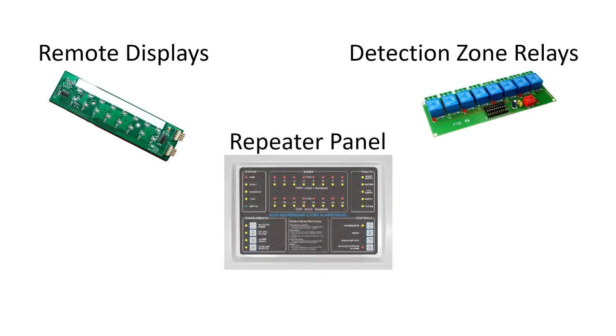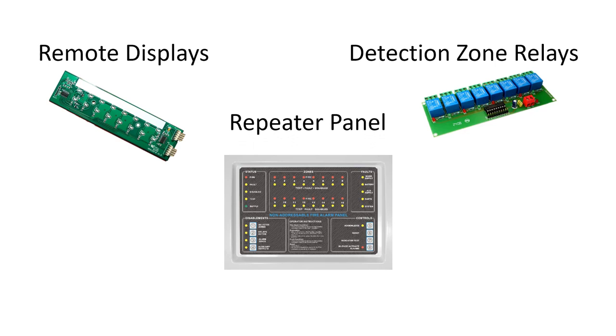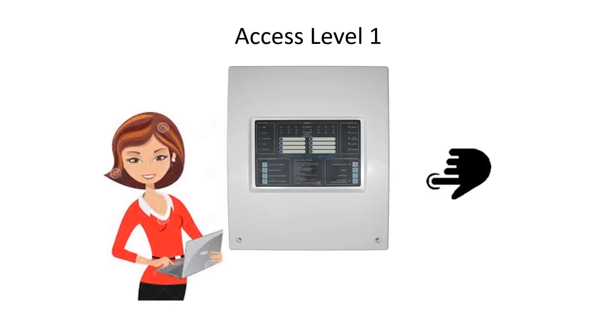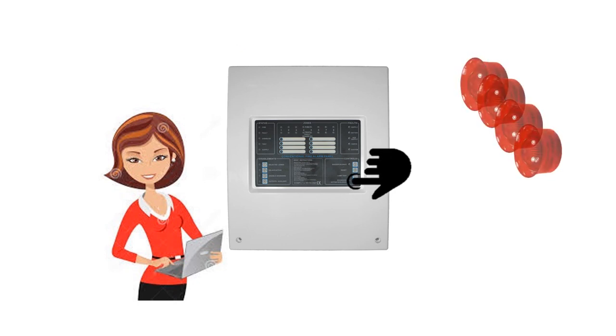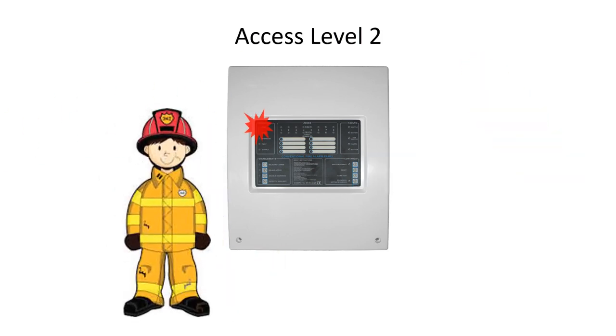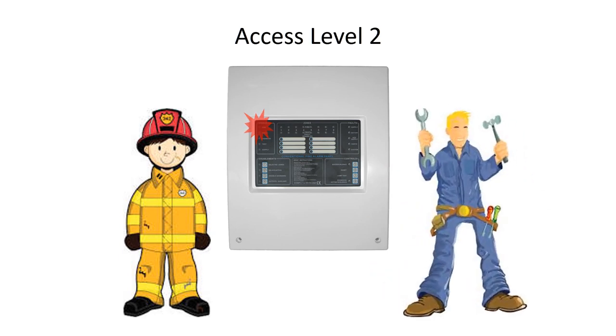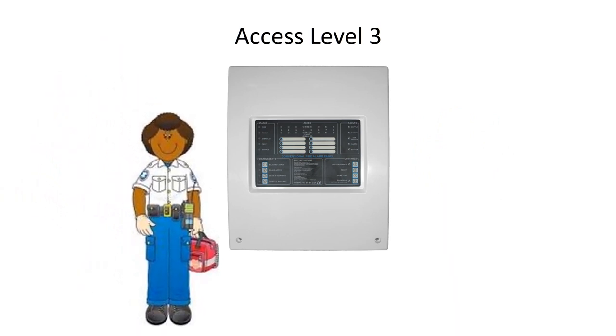A repeater panel extends the panel's controls and indicators to another location. Full control is available at the repeater panel, but no detectors or audio-visual alarm devices are connected to the repeater panel. The panel has 3 access levels that provide the required functions for the appropriate user. This may be an employee who needs to activate the audio-visual alarms to evacuate the building, or the fire brigade and site maintenance personnel who operate the panel in an emergency, or an installation technician who configures the panel.